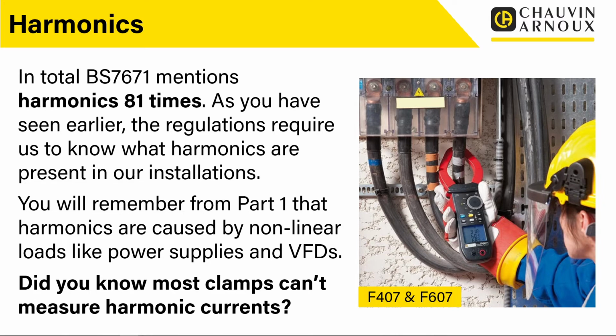Now, in the case of Chauvin Arnoux, we've got two clamps that are harmonic clamps, the F407 and the F607, and they're specifically designed to measure harmonics up to the 25th harmonic. So they will actually give you a true picture of what's going on. Something that's very important if you are measuring currents with a clamp meter and basing designs on that: always look at the manufacturer's data and make sure that it has the bandwidth to measure the harmonics as well as just the fundamental frequency.